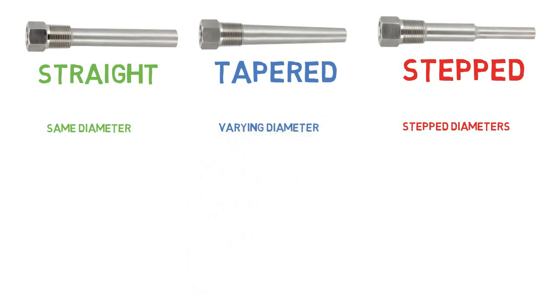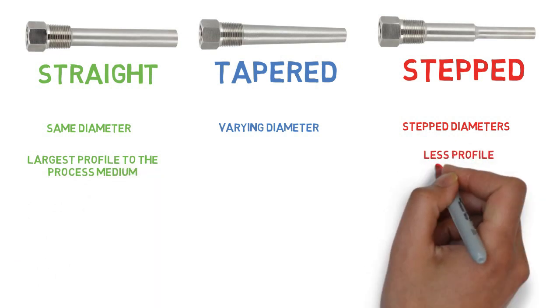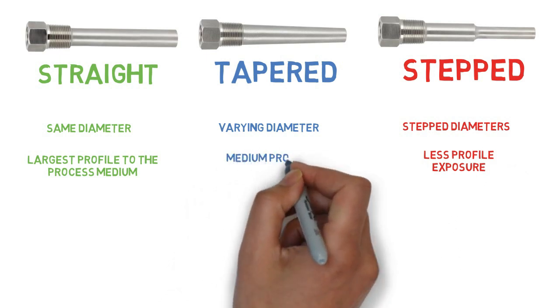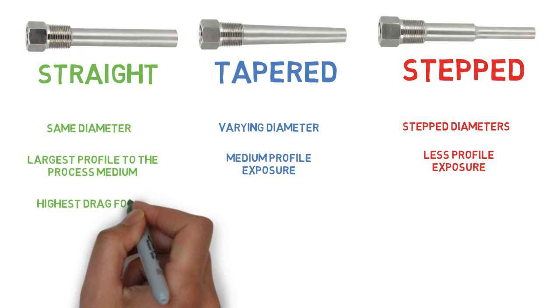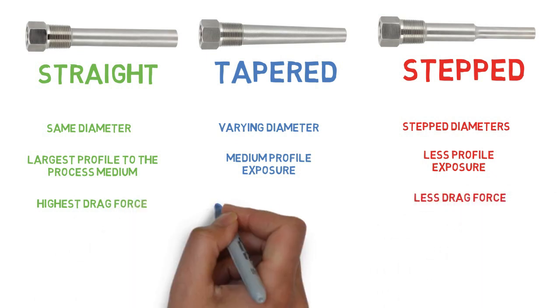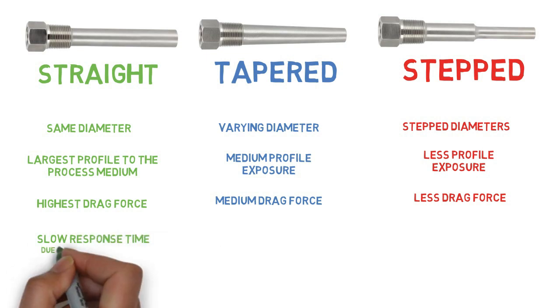A straight thermowell has the same diameter for the entire insertion length. A stepped thermowell has step diameters. A tapered thermowell has varying diameters over its full insertion length, with an outside diameter that decreases uniformly from root to tip. The straight type presents the largest profile to the process medium, the stepped design has less profile exposure for the same root diameter, and the tapered profile represents a good compromise between straight and tapered. The straight thermowell has the highest drag force; the stepped exhibits less drag force; the tapered has drag less than straight but greater than tapered.